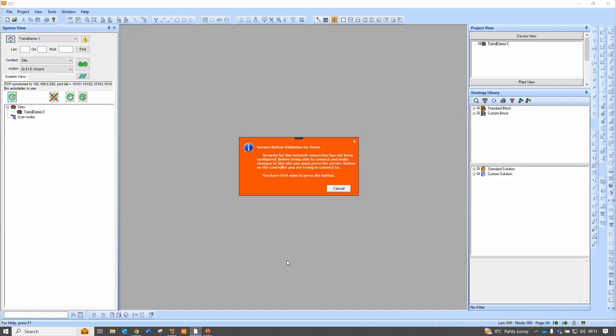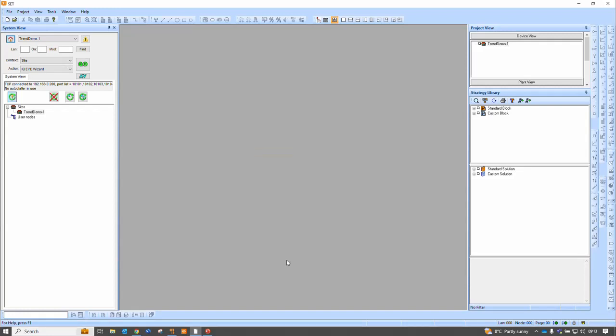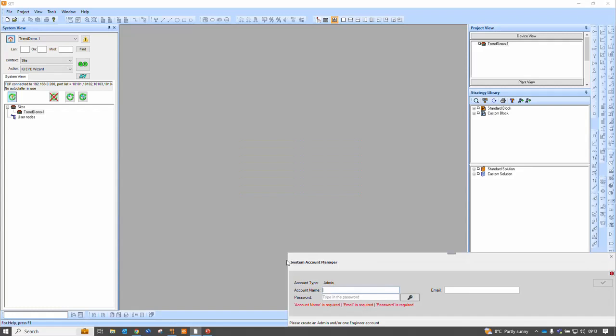Now, this is another security enhancement, which was the same in IQ4, in fact, and it means I need to prove that I'm physically on site and not trying to get in from outside somewhere. And what it requires me to do is physically press a button on the front of the controller, the service pin. That's that done. Luckily, my controllers are quite close to me. But you do have 10 minutes to go and find it.